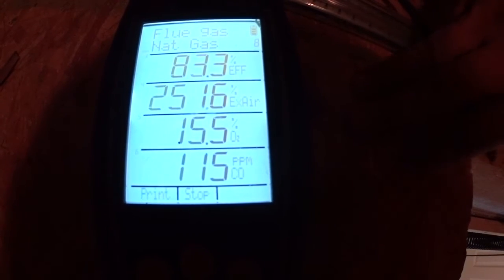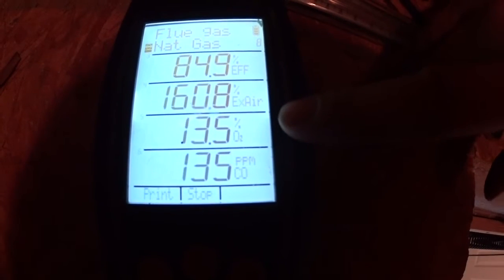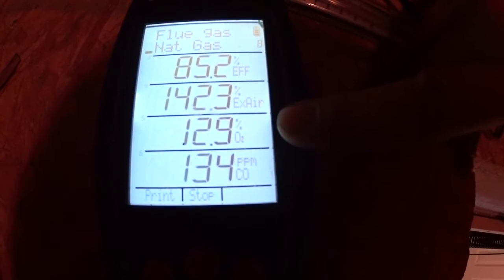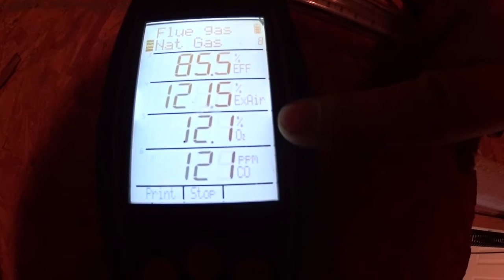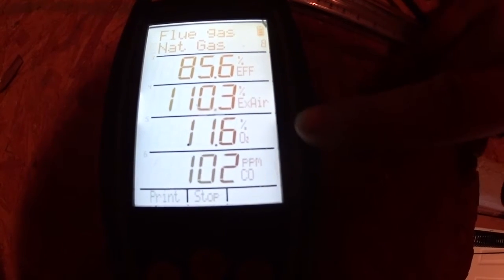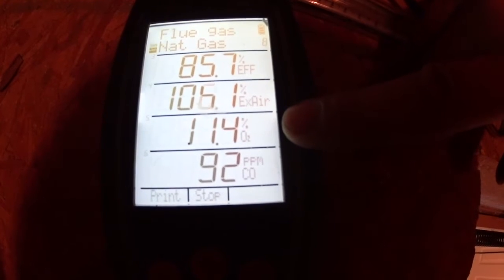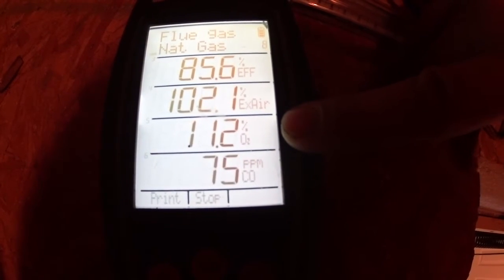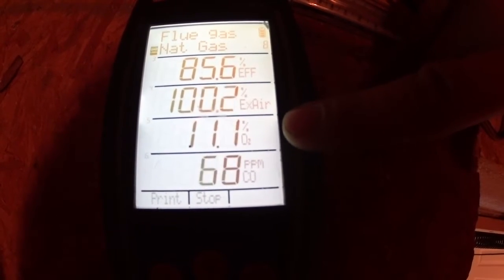Let's watch our oxygen now — our fan hasn't kicked on yet. We're waiting to hear our fan kick on, and as soon as it does, we'll watch our O2. It should not rise from this point. If it rises when the fan kicks on, there's a very good chance you have a crack in your heat exchanger.